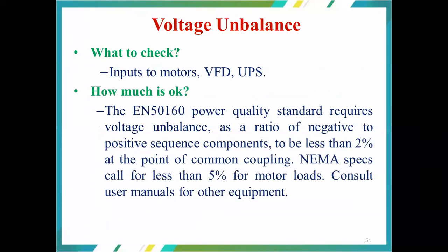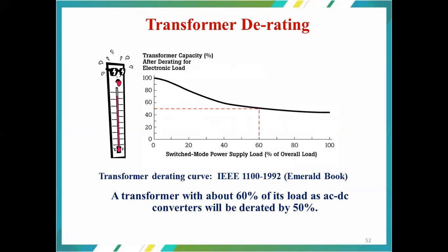When it comes to the unbalance, EN 50160 specifies that it should be less than 2% at the point of common coupling, and NEMA calls for less than 5% for motor loads. For a specific range, we are supposed to refer to the manuals of the particular equipment and the manufacturers. And as we already discussed, continuous harmonics presence in the local distribution network will derate the transformer at the particular locality. So a transformer with about 60% of its load being AC to DC converters will be derated by 50%.